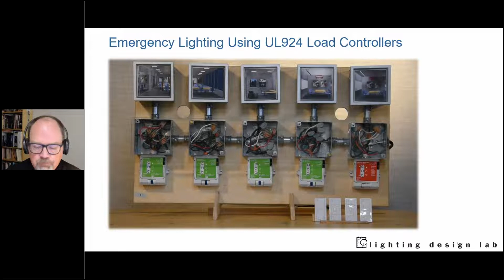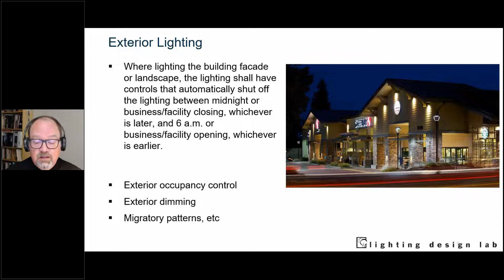Okay, let me go past that. All right, exterior lighting. I mentioned exterior lighting is becoming more complicated from a control standpoint. Depending on where you are, you're going to have scheduling—turning lights off or dimming them down at certain times. You might have things like migratory bird patterns to take into account with exterior dimming. Exterior occupancy sensor control is another one that's coming—parking lots, for example, will have occupancy sensors on the poles. Again, we don't want to dim down to zero because we don't want a dark, scary space, but we do want to harvest most of that lighting.